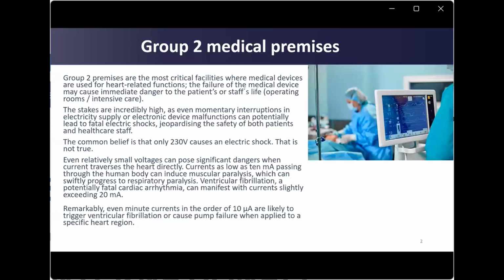Two are the most critical facilities where medical devices are used for heart-related functions. The failure of the medical device may cause immediate danger to the patient's and staff's life. The stakes are incredibly high, as even momentary interruptions in electricity supply or electronic device malfunctions can potentially lead to fatal electric shocks, jeopardizing the safety of both patients and healthcare staff.